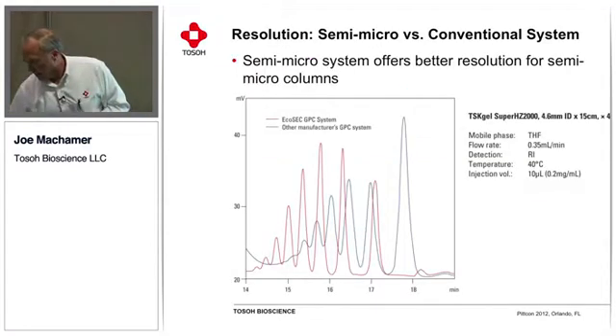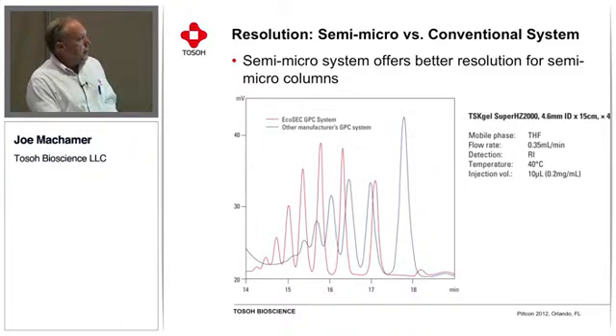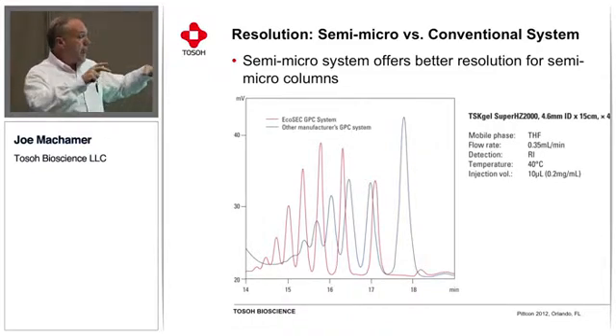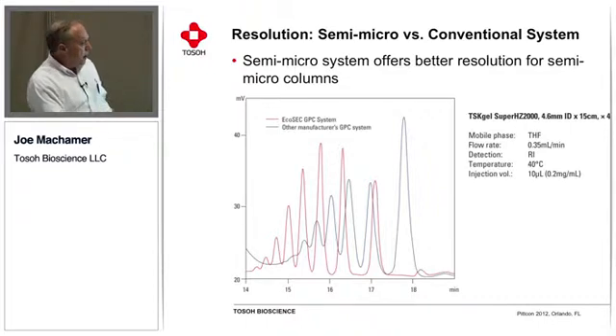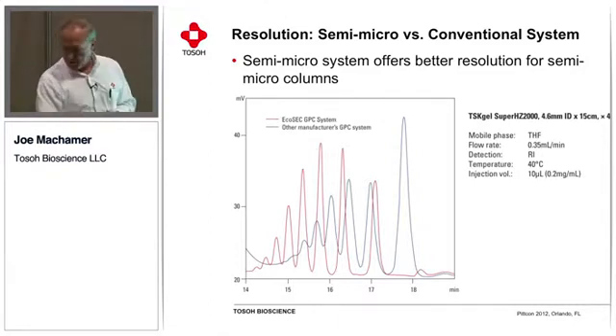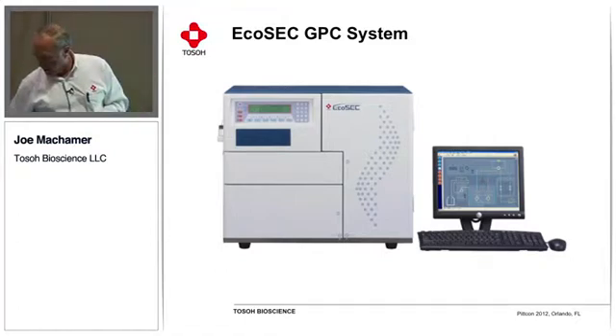a column. To show that, what we have here is a chromatogram using a SuperHZ column. Actually, we're using 4 of them, using THF as the mobile phase at 0.35 mL per minute. We are running the same column, samples and mobile phase, same flow rate, on 2 different systems. One system is our EcoSEC GPC system, which is designed to have very, very low dead volumes compared to a conventional GPC system. In purple, or red here, this is the resolution from the EcoSEC instrument, and essentially we're getting many more peaks with baseline resolution, and we're able to see many more peaks compared to running that same column and samples on a conventional system, and the reason for that is the lower dead volume of the system.